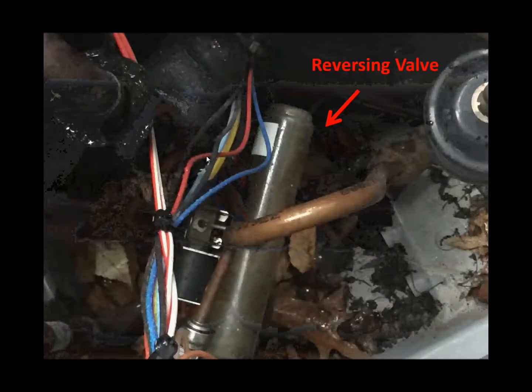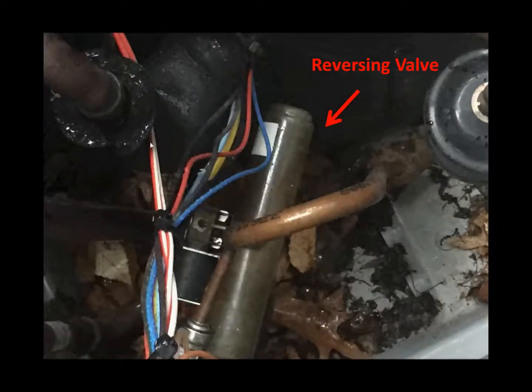Now here is one where I'm looking down through my unit at my house, trying to see the reversing valve, and it's kind of dark down in there, but you can see it. Here's that magnetic coil. Here's that long tube thing, and here are the other pipes going into it. And in the next slide, you'll be able to see that better. I actually found a better place and shined some light down in there so you can see it better. And this is what a reversing valve looks like installed in the heat pump.